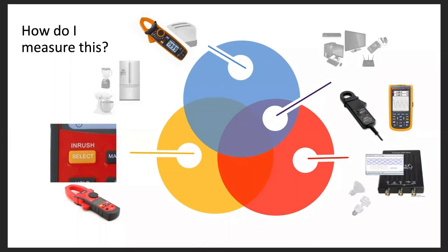Don't expect that anyone will buy, or I would not even recommend that everyone buy, a field O-scope to measure transient voltages. Really what I would do is just try to avoid big banks of fluorescent lights and any home offices, especially with laser printers and a lot of switch mode power supply consumer electronics. Maybe put those behind a small UPS to, again, avoid nuisance trips of the battery when in off-grid mode.